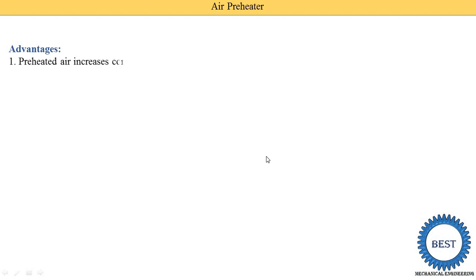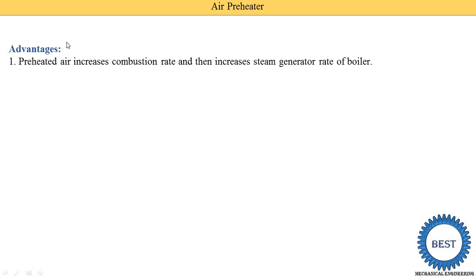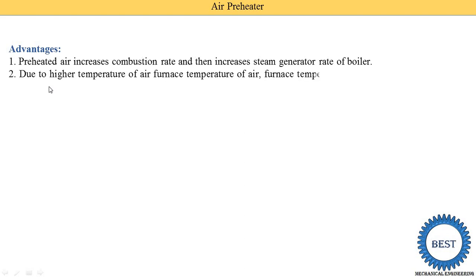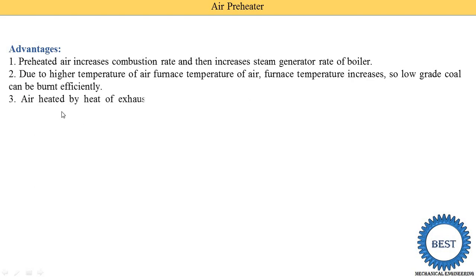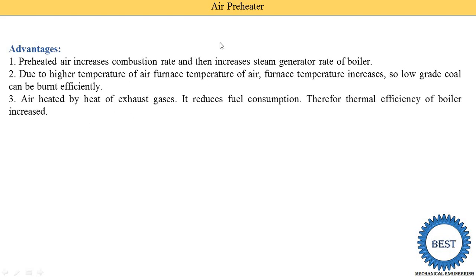The advantages of an air preheater: preheated air increases the combustion rate and increases the steam generation rate of the boiler. Due to the higher temperature of air, the furnace temperature is increased, so low-grade coal can be burned efficiently. The air is heated using the heat of exhaust gases, which reduces fuel consumption and therefore increases the thermal efficiency of the boiler.